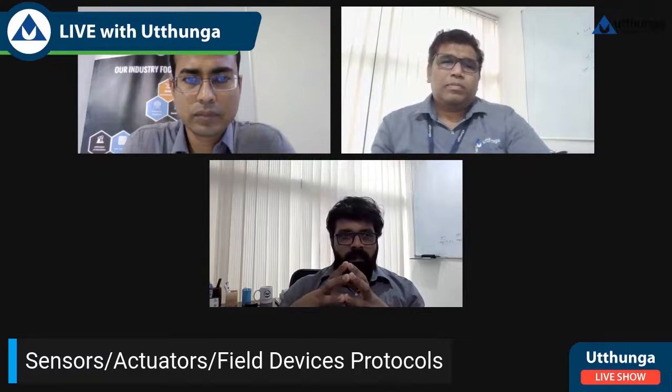And now, recently, definitely, IO-Link is also playing a major role. So IO-Link needed extra power, but IO-Link has a lot of features when we are discussing sensors and actuators. Specifically, similar to how we are using it in HART, there is an IO-Link device descriptor file. It's known as IODD, which will define the various configurations and parameters specific to the sensors and actuators. Again, these things are working on master slave principles.